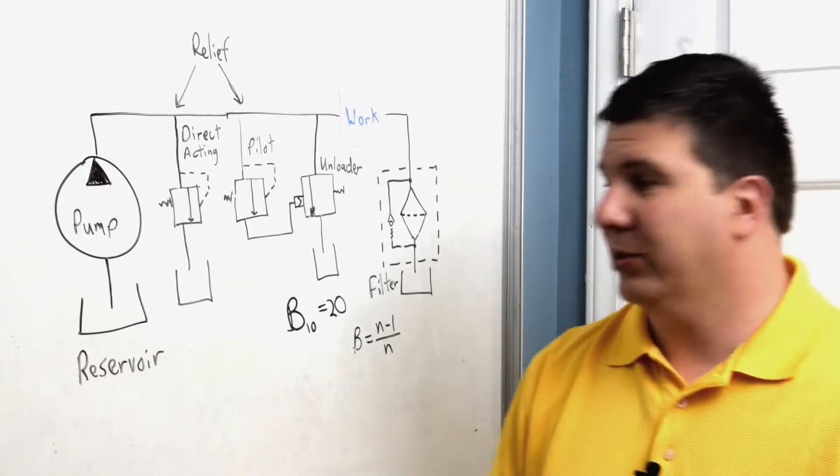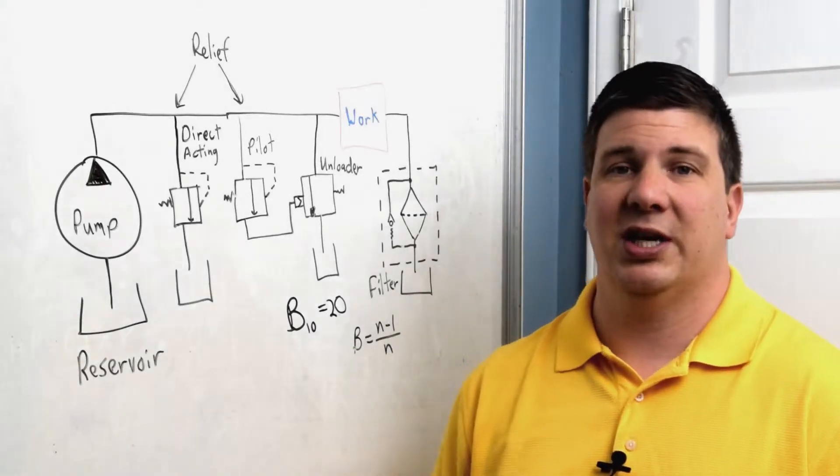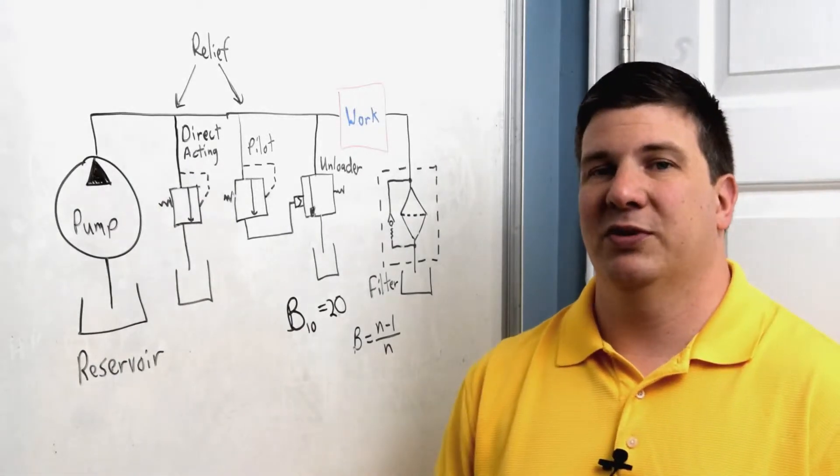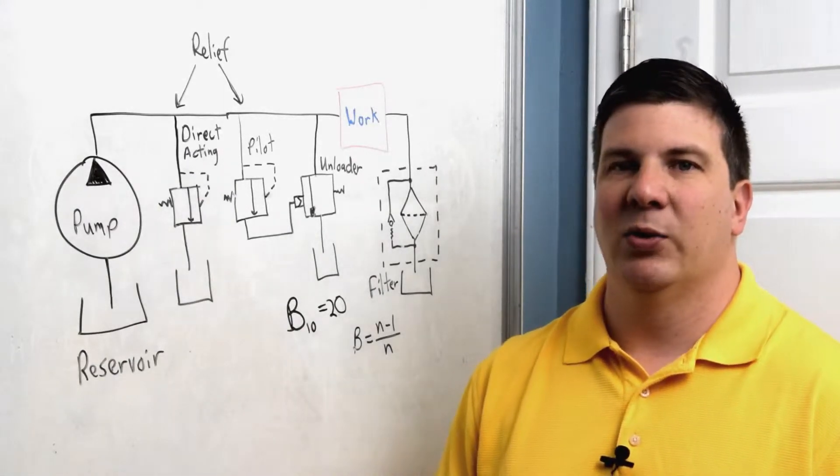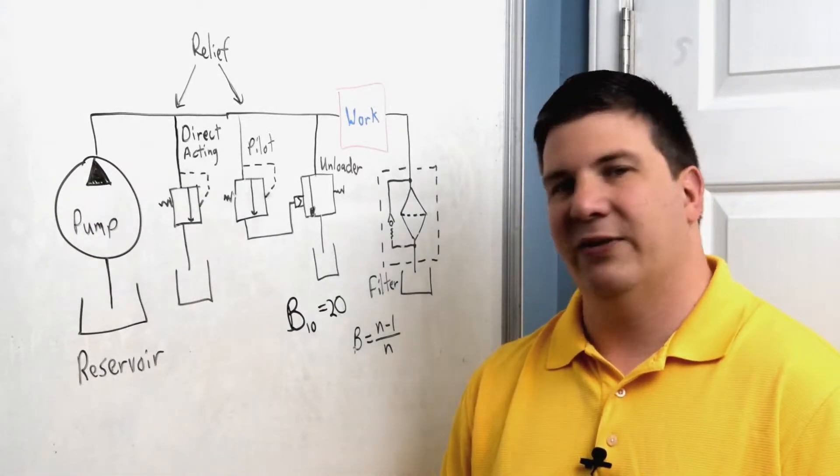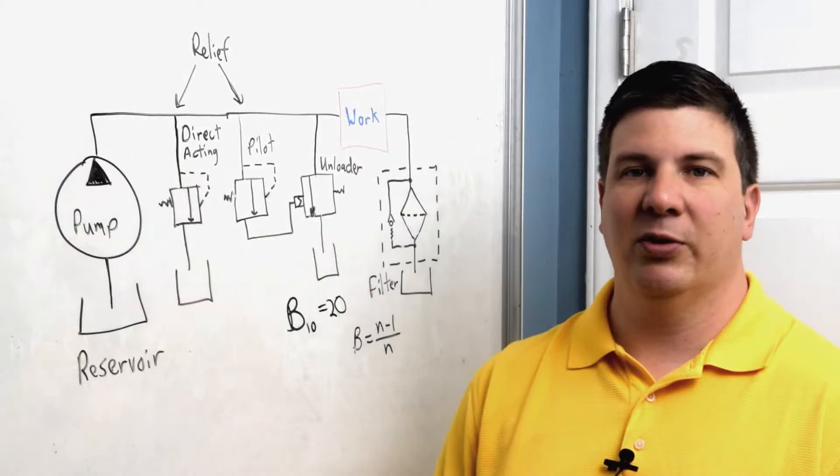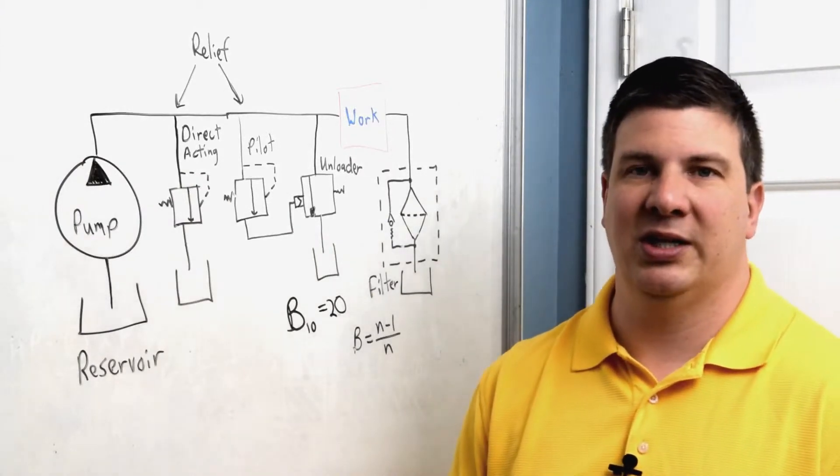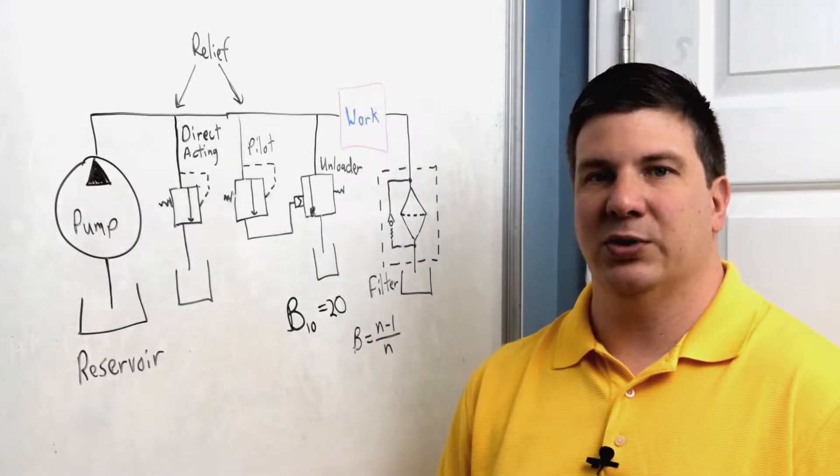Let's talk about reservoirs. A reservoir is a large container of oil. The general rule of thumb is whatever your flow rate is, you need three times of that in hydraulic oil storage. So if I have a 10 gallon per minute flow rate, I need 30 gallons in oil storage.